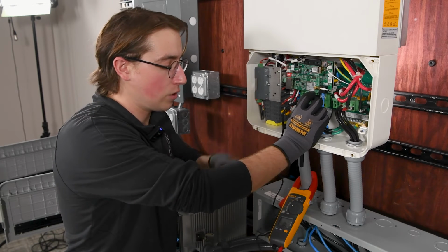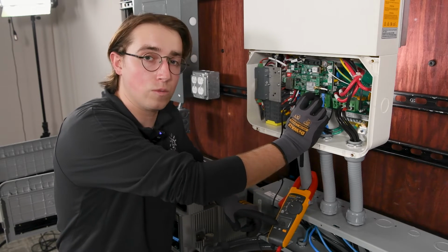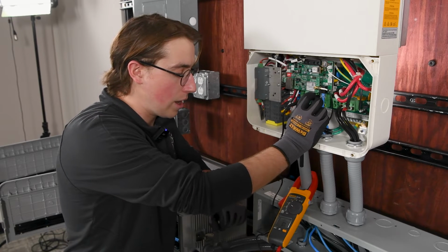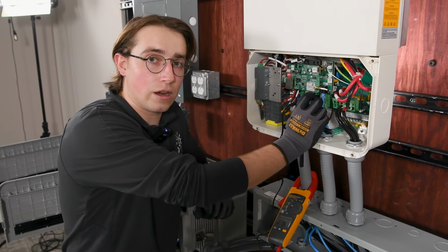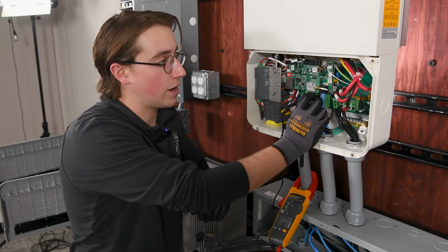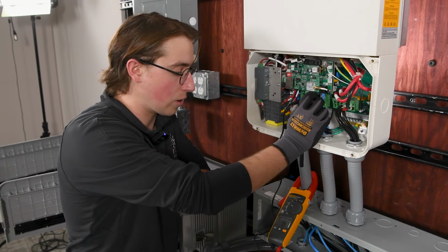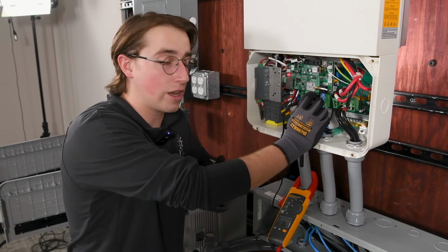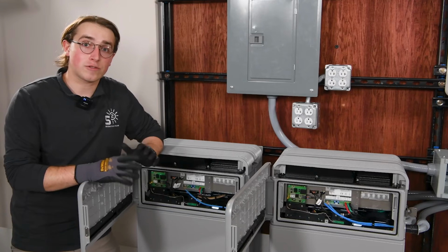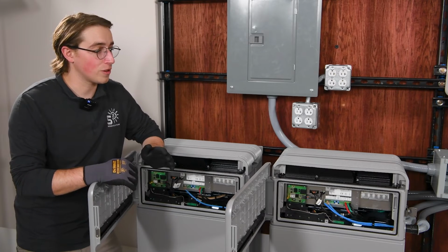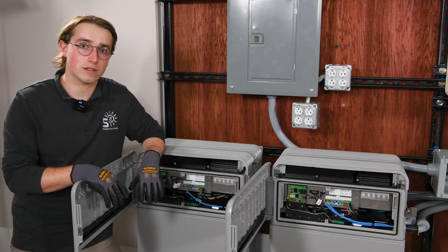If you're getting a continuous beep and we see 0 ohms across our multimeter, then there is a short somewhere and we need to identify that. But for right now, it looks like we are not seeing any continuity between positive and negative, which is a great sign. After performing our continuity test, we ensured that there is no cross polarity happening between positive and negative.